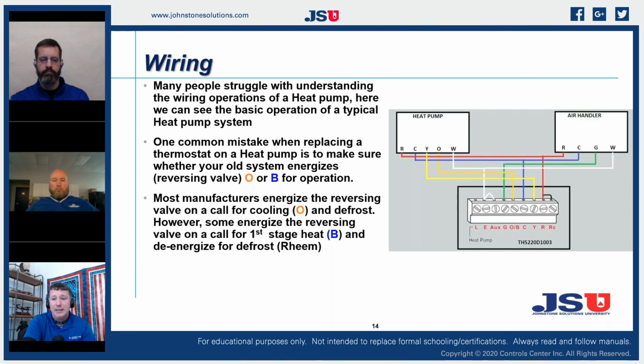When we get into wiring, it's really important to understand the difference between O and B on an operating system. For most of our heat pumps, we're going to be operating with the same principle. We're going to be using Y to bring on our compressor. We're going to be using W to bring on our auxiliary heat or our electric heat. And then we're going to be reversing our reversing valve with O/B. And not everyone understands the difference between those.